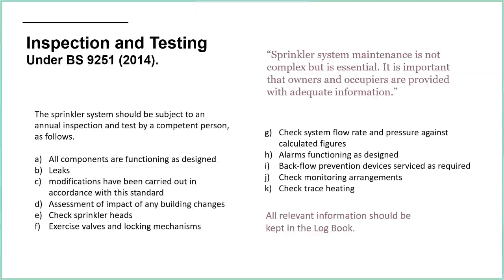So let's go through what is required. This is an annual test at a minimum. So I need to point that out: a minimum of an annual test by a competent person. All components are functioning as designed. I like that one. It's kind of a catch-all, isn't it? Is everything working? Obviously the pump, obviously the alarm devices, also the valves, and anything else that you've got on there, any monitoring equipment, any panels. Is everything working as designed?